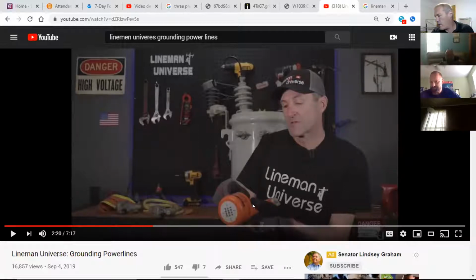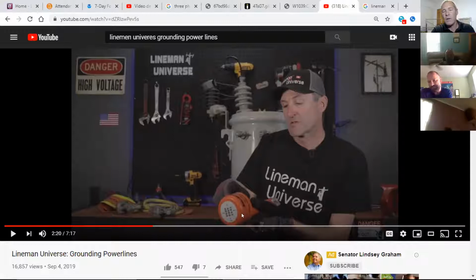Now, here's a warning, gentlemen, and this happened probably about 10 years ago. I seriously doubt they're being made anymore, but they're still out there. There were tick tracers or hot horns that made a solid tone all the time, and when you got them close to an energized conductor, they went quiet. They worked in the exact opposite concept.